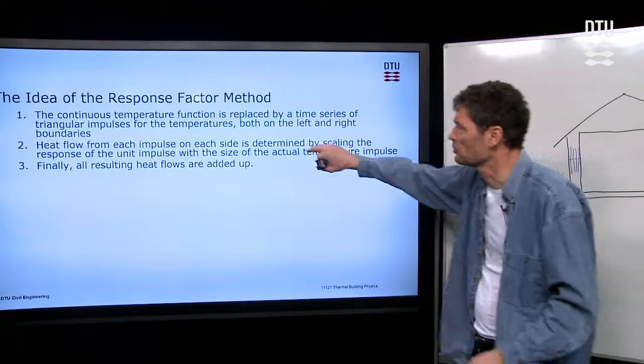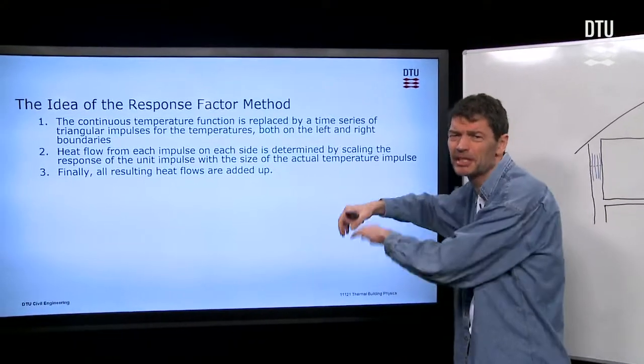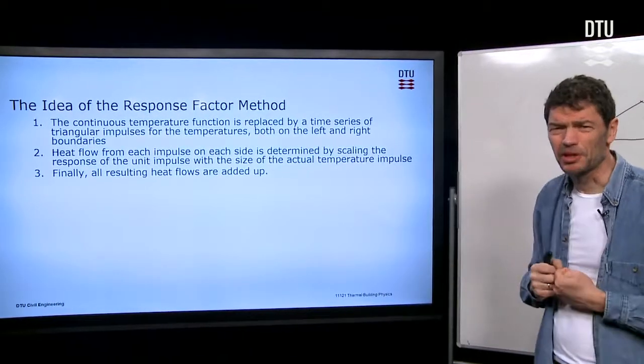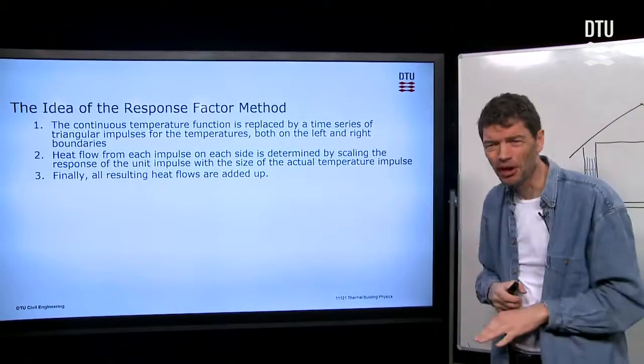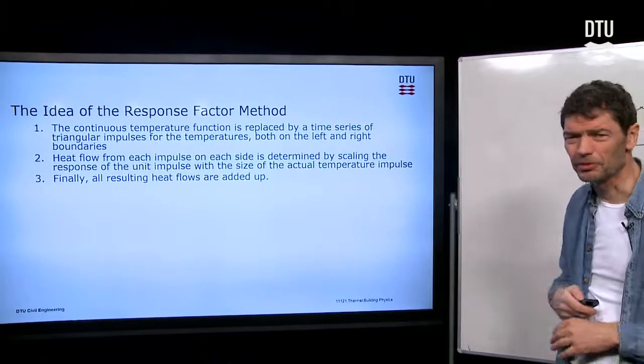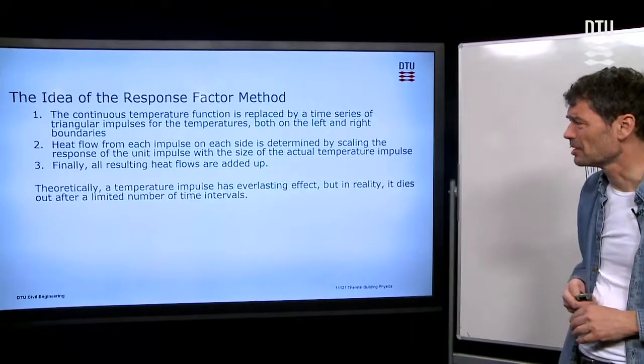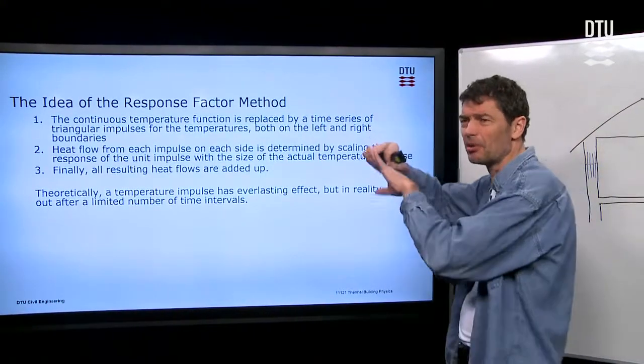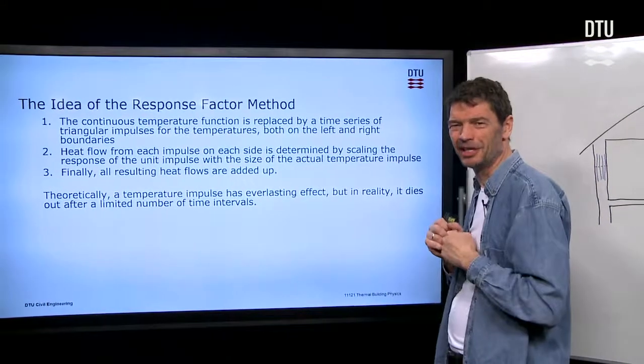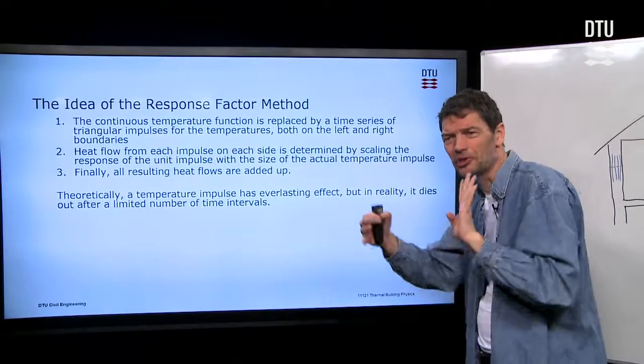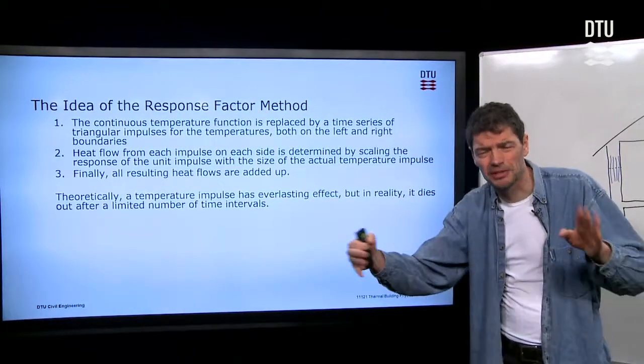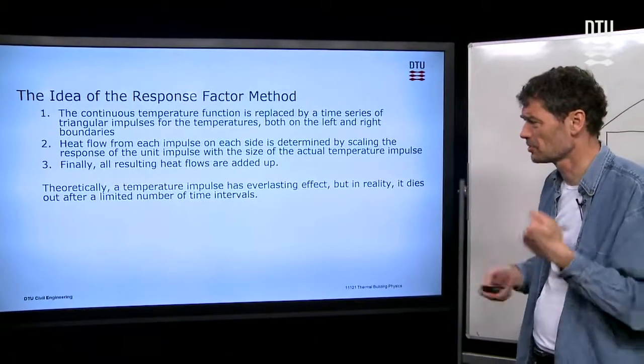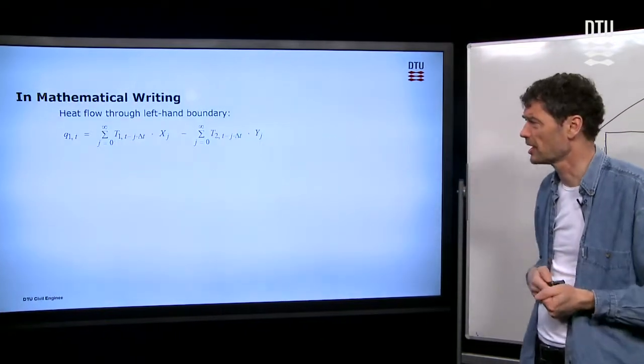And we scale the whole thing, so we work with unit impulses, and then we can scale it by multiplication with the real temperature impulses. And everything is then added up back in time with all those time series. One thing is that if we have a temperature impulse on a wall, theoretically it will last forever. But in reality, things die out, so we need only remember the time series, the X factors, Y factors, and Z factors, for a certain number of hours, typically. So therefore, it's somewhat practical to calculate this.